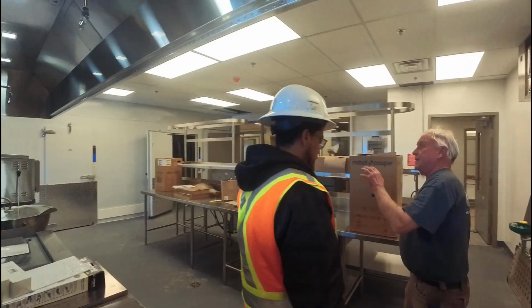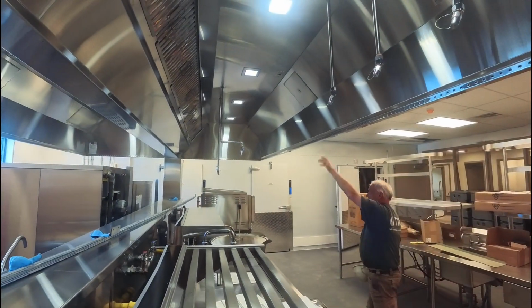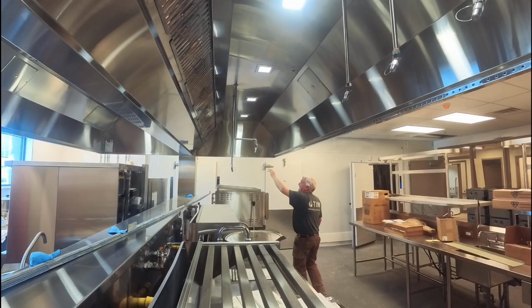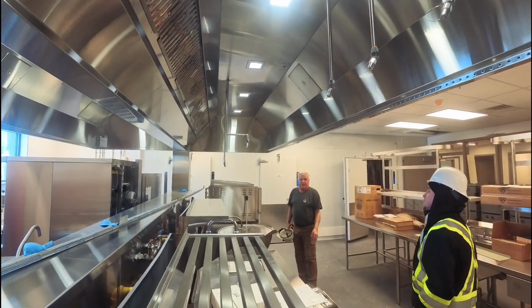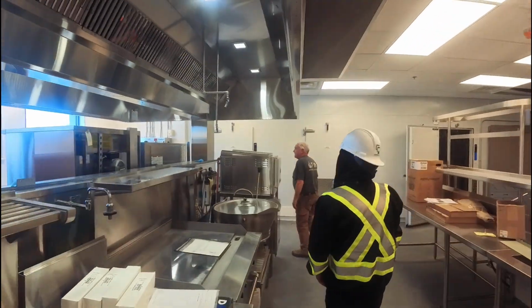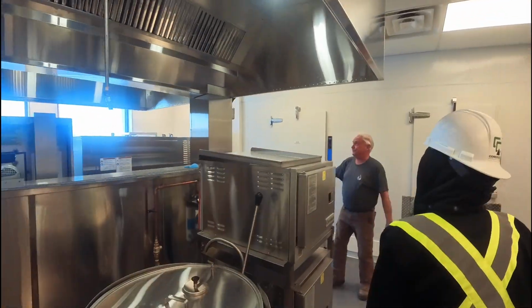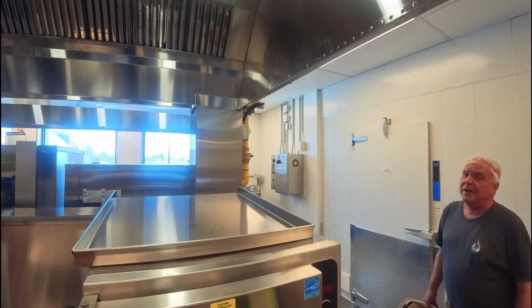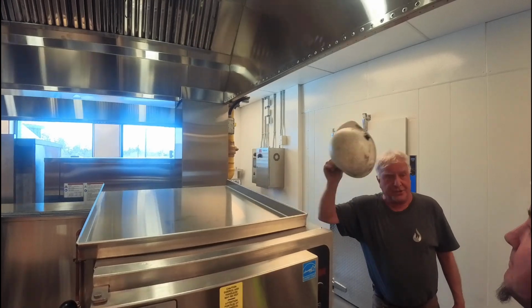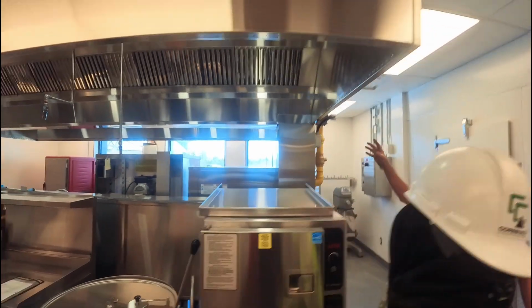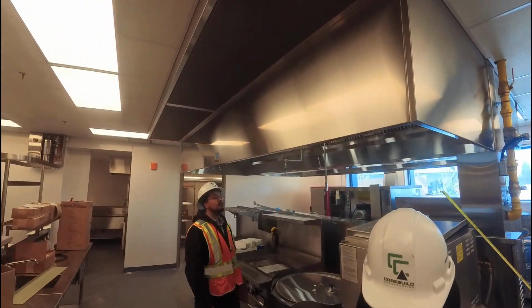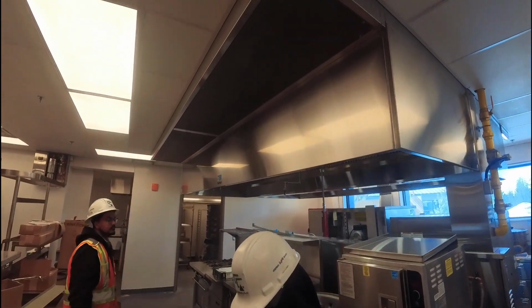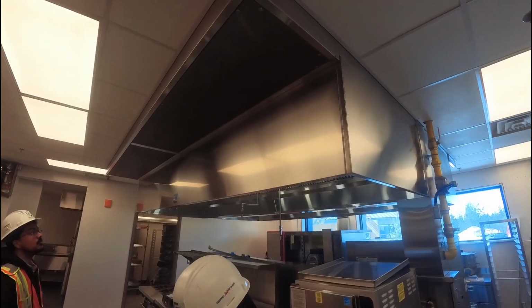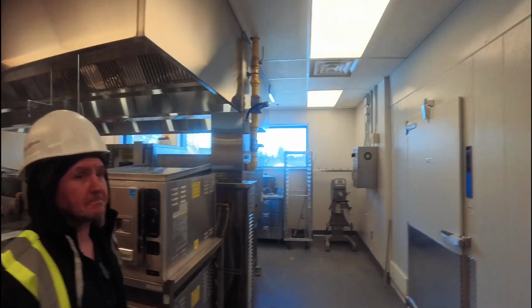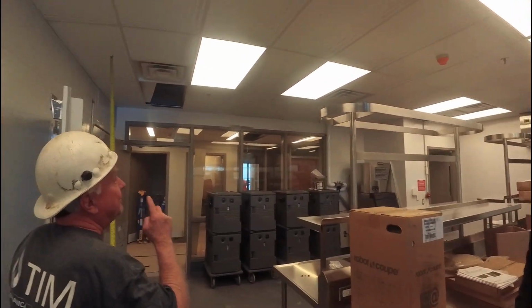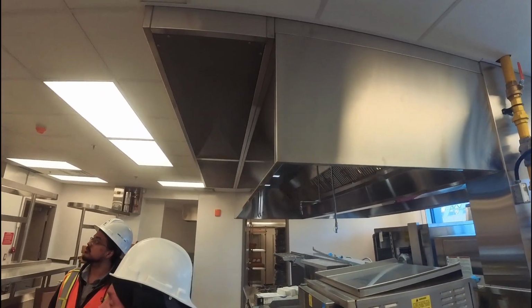Also associated with the kitchen, the exhaust hood for all the cooking, the heat, the steam, the grease, everything like that goes through a series of filters. I'm sure you'll learn all that when you do your kitchen training, etc. Run through that VFD as well. When that turns this on, based on appliances being turned on, the hood comes on, the exhaust fan on the roof turns on the makeup air, because we're pulling so much air out of here that we have to have makeup air put back in, or relief air, whatever you'd like to call it. That unit sits directly above us on the roof up here in this corner. The duct traverses down the hall, or down this aisleway.